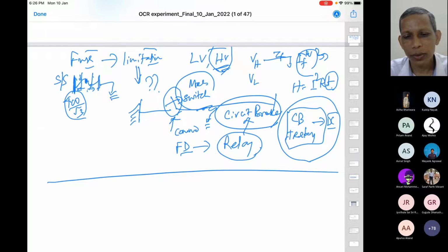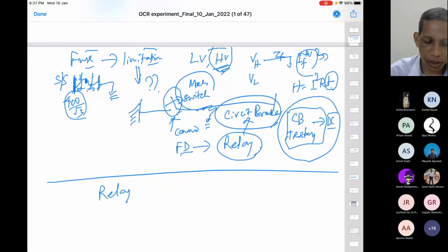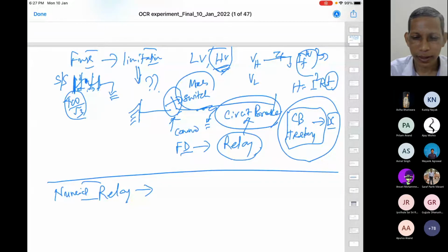So, what is that relay? We will not discuss the breaker part here. Our discussions, our experimentation here is on the relay part only. Agree? So for this relay, you will still find numerical relay in the industry in electromagnetic relay and also static, because of the cost issue, investment issue. But numerical has enormous advantages. Just like any digital device, it has positive points such as self-checking. One major point is that you can store the data, and then you can have the postmortem analysis of the system.